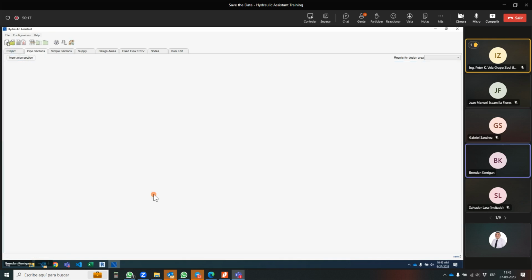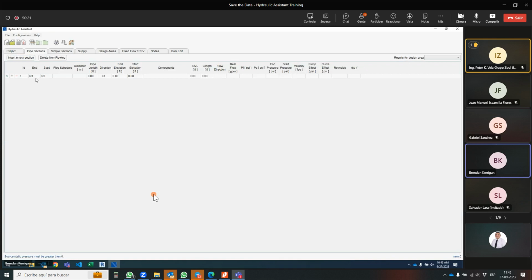If you want to go with the other method, it's really designed around working your way back along a branch line. So if we had S1 to S2, schedule 40 pipe, 1.5 inch, and it's like 10 feet long, I can type 10 feet, 20 feet, 20 feet. If you click this leftmost one, you'll see it carries on the naming. It fills in the next node here with the last one, and then it populates a new node name for you. So it would be S2 to S3, S4, or however you want to name it. What it's doing is copying information over and filling it in a little bit for you. So if you're working your way back a branch line, it might save you some time. Otherwise, it might be wasting some of your time. So pick exactly what you're looking to do.